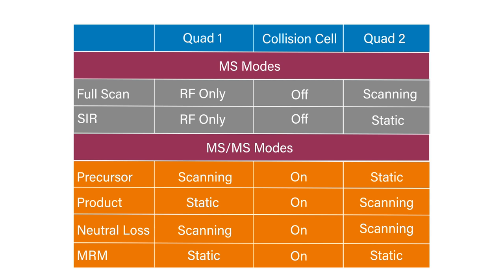Sometimes, when working with a tandem quadrupole instrument, we talk about doing MS or MS-MS acquisitions. An MS acquisition is when we set just one of the quadrupoles to either static or scanning mode, while the other quadrupole is set with an RF voltage only and no DC voltage.